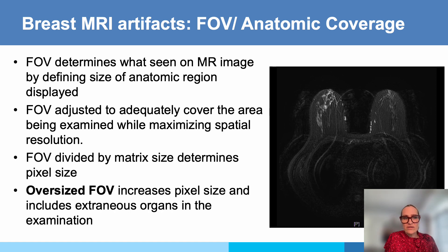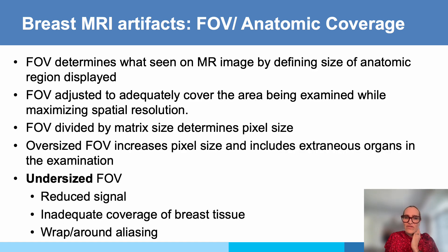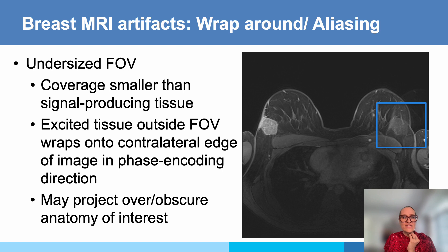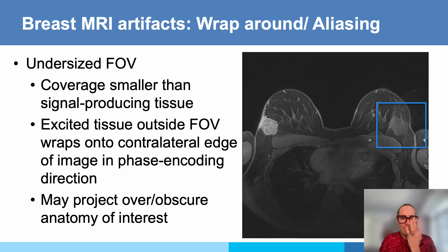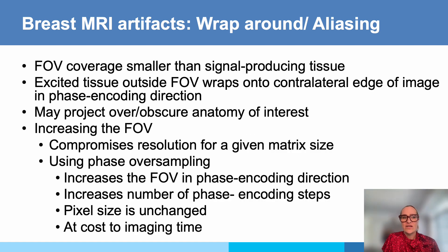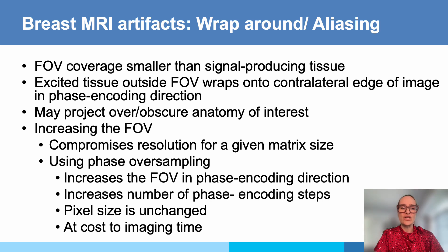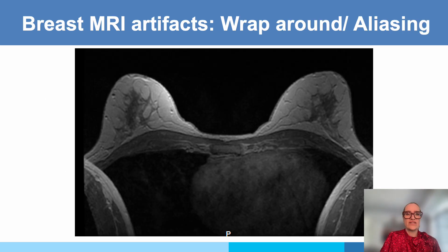Anatomic coverage is very important. An oversized field of view increases pixel size and includes extraneous organs you don't need — we want to cover just the area of interest. When the field of view is too small, you have reduced signal, inadequate coverage, and most often wrap-around aliasing artifacts, as seen here with the arm wrapping into the anatomy. The technologist usually spots this immediately and adjusts the field of view to eliminate such wraparound artifacts.